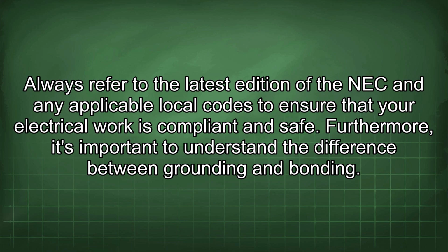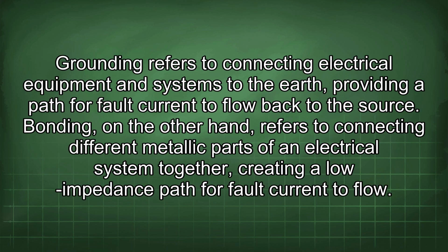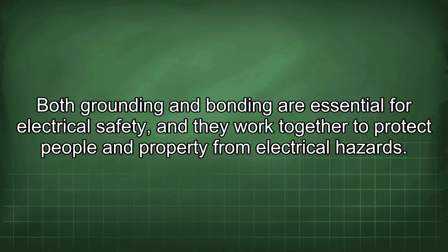Furthermore, it's important to understand the difference between grounding and bonding. Grounding refers to connecting electrical equipment and systems to the earth, providing a path for fault current to flow back to the source. Bonding, on the other hand, refers to connecting different metallic parts of an electrical system together, creating a low impedance path for fault current to flow. Both grounding and bonding are essential for electrical safety, and they work together to protect people and property from electrical hazards.